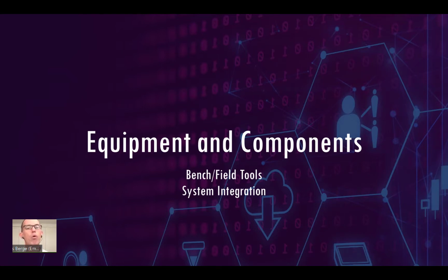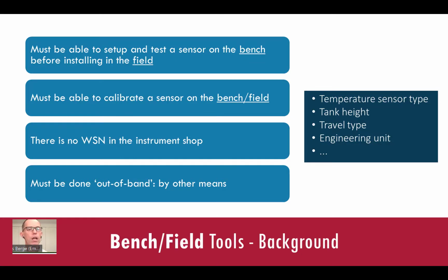life. Let's look at portable tools for the workshop workbench and for field work, and then integration of sensors and gateways into existing control systems. You must be able to set up the wireless sensors on the bench in the instrument shop. This may include sensor type selection for a temperature transmitter or a tank height setting for a level transmitter, and to function test before installing it in the field. And you must be able to calibrate the sensor in the field or on the bench using a portable calibrator.